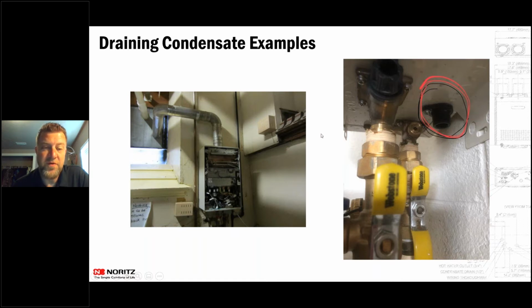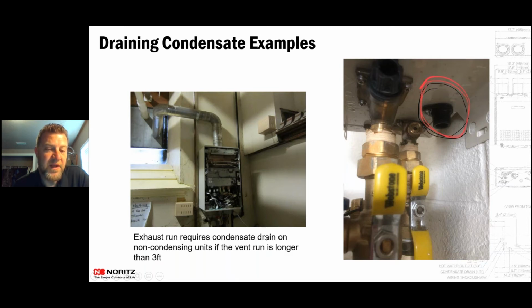With older units that you would see out here, this picture on the left is a non-condensing unit. You can see that it is run just in that 4-inch stainless steel going up and out. But any unit that has a vent run that's longer than 3 feet, even with non-condensing, you're still going to get a little bit of condensation in there, because of the temperature change from the flue gases to the ambient temperature around it. So typically, if you were running it 3 feet or longer, you would put in a condensate trap. As you can see, this one does not have one piped up here on the top.